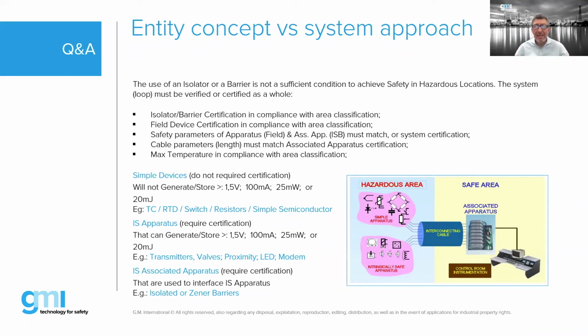Do you remember we discussed cable capacitance last time? We had a similar question. Yeah, I asked my friend, the manufacturer of cabling, about capacitance. The shield, if I remember correctly, increases the capacitance of the cable, right? It does increase the capacitance. Yes. So I believe the numbers you have to use are the ones specified by the manufacturer. The manufacturer will give you the maximum capacitance per meter or per feet or per kilometer. Right. You just enter that data.